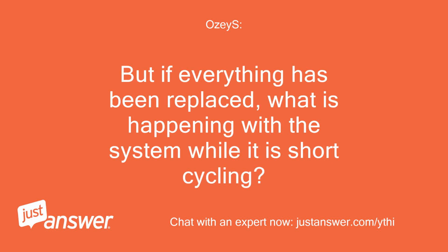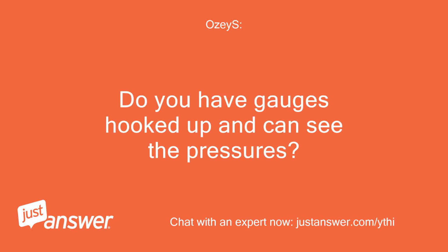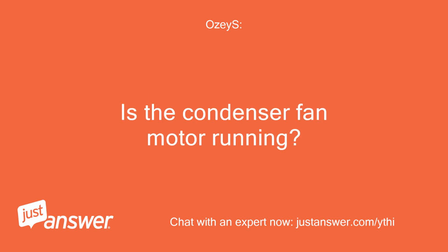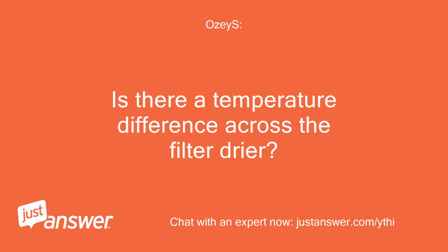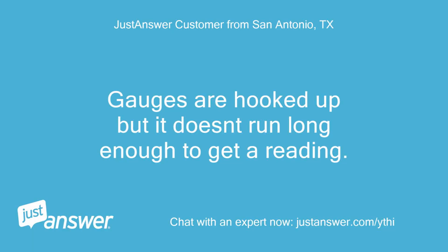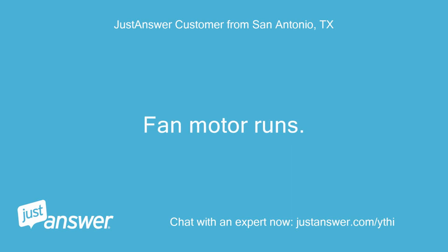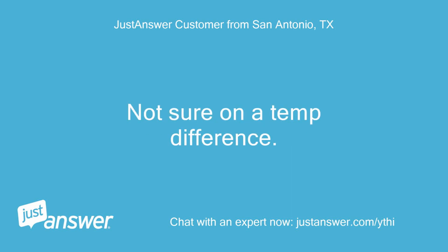But if everything has been replaced, what is happening with the system while it is short cycling? Do you have gauges hooked up and can see the pressures? Is the condenser fan motor running? Is there a temperature difference across the filter dryer? Gauges are hooked up but it doesn't run long enough to get a reading. Fan motor runs. Not sure on a temp difference.